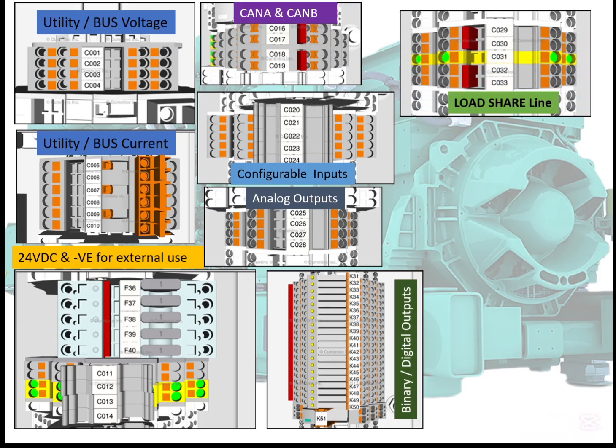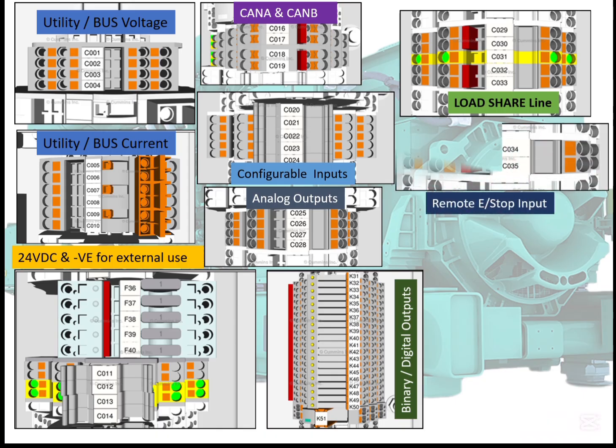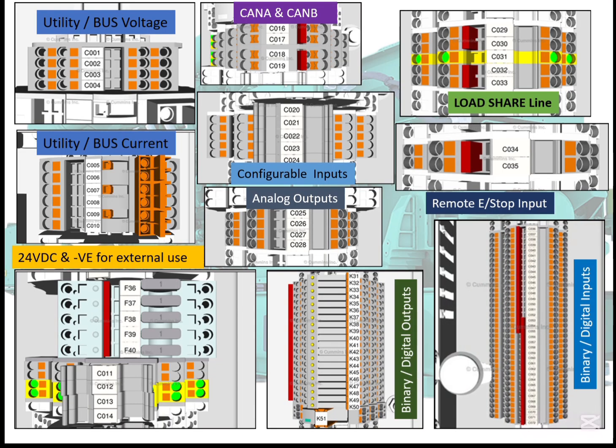Load share lines are located from C31 to C33, with 29 and 30 for external voltage biasing. C34 and C35 are the remote emergency stop input, needed for K51 as output. These are the binary inputs, C036 to C072: remote start, load demand stop, customer faults, HTLT level tank low, fan trip, radiator fan trip, earth fault, differential fault, DCB trip, utility DCB trip, genset position. So all the inputs are labeled here where we can connect our external equipment.